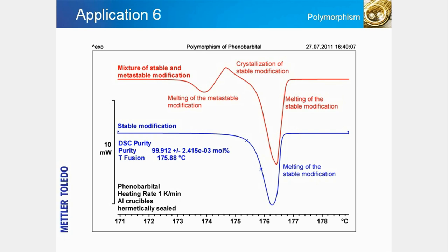Analysis of the melting behavior of a substance is an important method used for the quality control of pharmaceutical products. The melting curve yields information about polymorphism and allows the degree of purity to be determined. For example, the red curve shows that the metastable modification of the substance melts at a lower temperature than the stable modification. The melt then crystallizes to the stable modification and afterwards melts at a higher temperature. The percentage purity of a substance can be determined by evaluating the melting curve using a method based on the Van't Hoff equation, as shown by the blue curve for the stable form of phenobarbital.